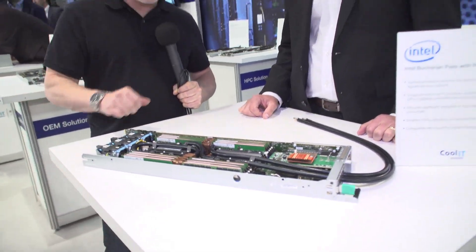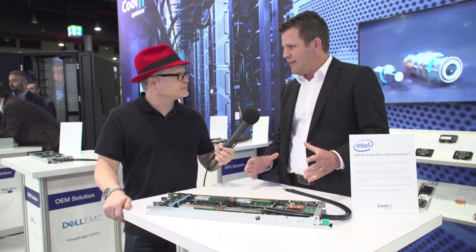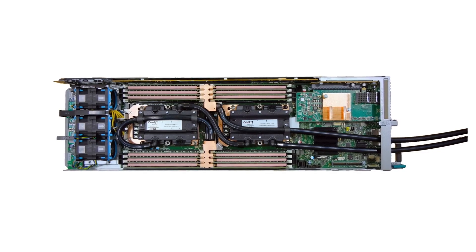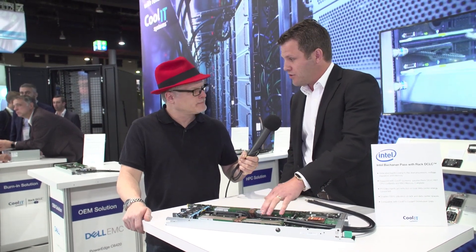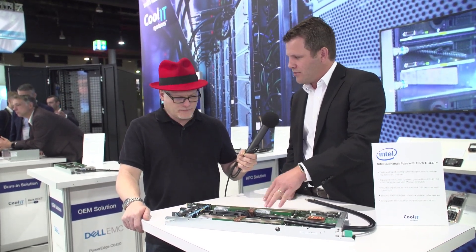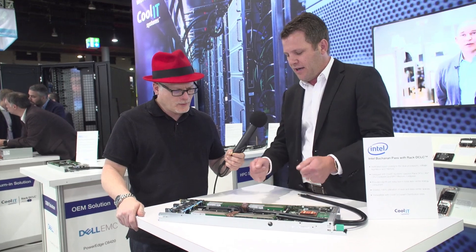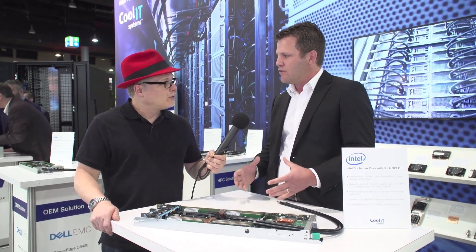This is a different kind of setup — what are we looking at? It's a different configuration. This is CoolIT's design for the Intel Buchanan Pass server. It's a 2U 4-node server, similar to the Dell C6420. But in this configuration we're cooling both the Skylake sockets as well as the voltage regulators from the CPU, and all of the DIMMs are also liquid cooled. It's a very unique design where the cold plate stays with the chassis and allows the DIMMs to be removed individually for service. This cools 85% or better of all server energy loads into the liquid path.